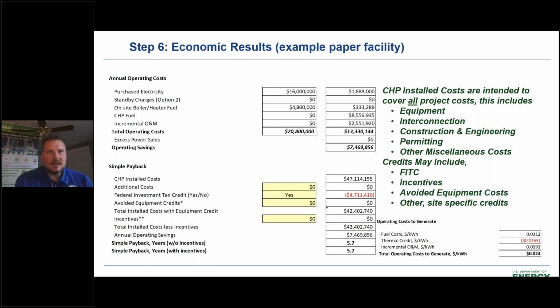Now we look at the economic results. Remember, this is a screening analysis, a first cut to see if there's potential for a CHP project, often leading to a recommendation for a feasibility study, or something in between. Looking at purchased electricity, in the base case we're paying $16 million. In the CHP case, we're spending less than $2 million because we're generating so much. For the boiler case, we used $4.8 million to generate thermal energy; in the CHP case, only $333,000 for boiler fuel. But we also have fuel for the CHP system itself, $8.5 million, plus incremental O&M of about $2.5 million. Still, there are operating savings of nearly $7.5 million for this project.